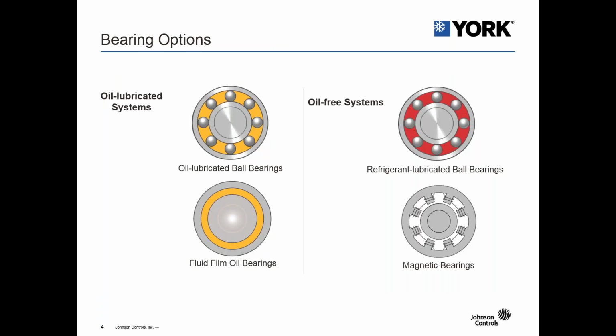So let's move on to bearing options. On the left-hand side, you'll see the traditional oil lubricated systems. So you have a oil lubricated ball bearing and also a fluid film oil bearing. And on the right-hand side, you'll see the oil-free systems. In the top right-hand corner, you'll see the refrigerant lubricated ball bearing, which is very similar to the oil lubricated ball bearing, where it uses refrigerant instead of oil as the lubrication system. And then in the bottom right, the only one of these that is truly lubrication-free is the magnetic bearings.